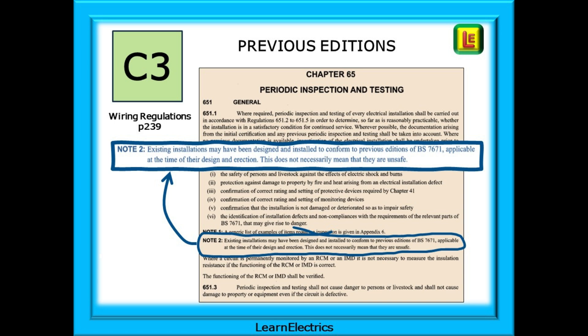A very common question is: what about plastic consumer units? The regulations now state that consumer units should be constructed from non-combustible materials, which means metal to most of us. If the property has a plastic consumer unit that was installed to a previous edition of the regs when plastic was acceptable, and it is still working as intended, then there is no requirement to change it to a metal one. We will record a C3 and suggest to the customer that metal consumer units offer better fire safety, and leave it at that. If the client says no, then that is fine — your obligation is to tell them, and that is now complete.